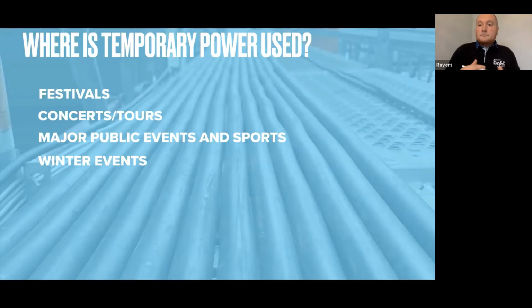With a bit of careful trickery, you can box quite clever and power big shows from stadium and venue supplies. For example, Wembley Stadium has a switchover system between various substations coming into the building, and they use UPSs, essentially big batteries, to bridge the gap in supply. So if there's a failure, those batteries take the full load for a momentary minute of time before the systems can switch over to a backup substation.